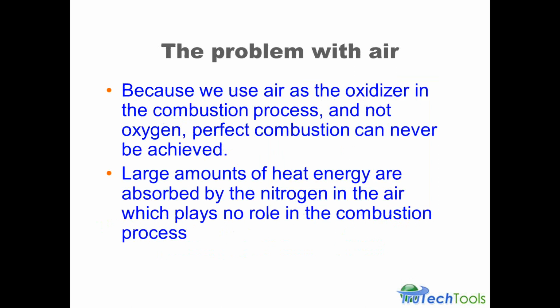So here we talk about the problem with using air, if you want to call it a problem. It's very convenient. It's around us, but because the air we use is the oxidizer, and it contains only partially oxygen and the rest nitrogen, perfect combustion can never be achieved. There's always that additional nitrogen there interfering with things. Also, large amounts of heat energy are absorbed by the nitrogen in the air as it moves through the combustion system, and that plays no role in the combustion process. That just moves up the stack.